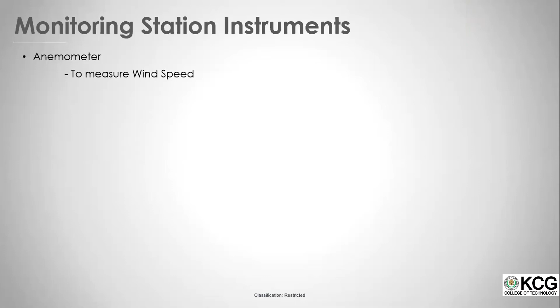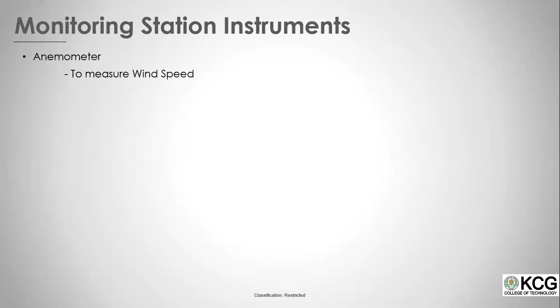As we have seen about the met mast, Naveen was talking about different sensors that could be installed in the met mast. I'll take you through the different types of sensors. First, the anemometer, an instrument used to measure wind speed. There are various types of anemometers used in the standards. The first type is the cup anemometer, connected to a vertical rotating shaft. The wind causes the assembly to turn. A transducer in the anemometer converts this rotational movement into electrical signals, which are sent through a wire to the data logger. The logger measures the frequency of these signals and converts it into wind speeds. This is the basics of how it occurs.